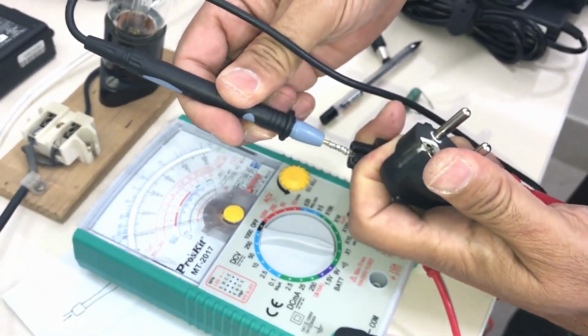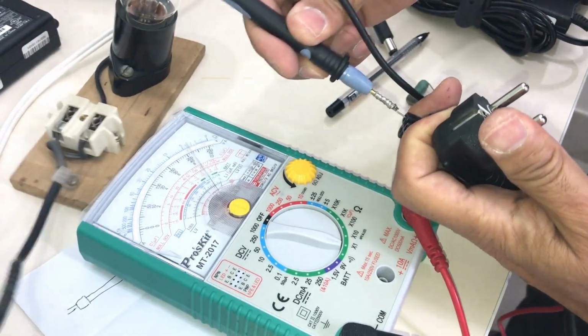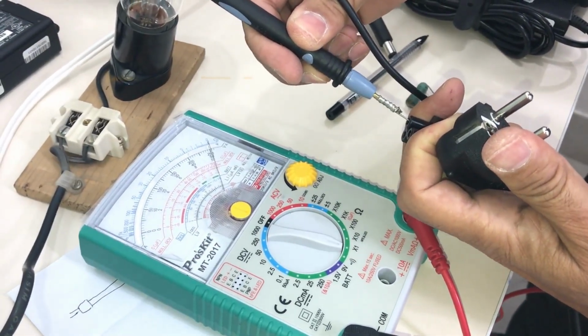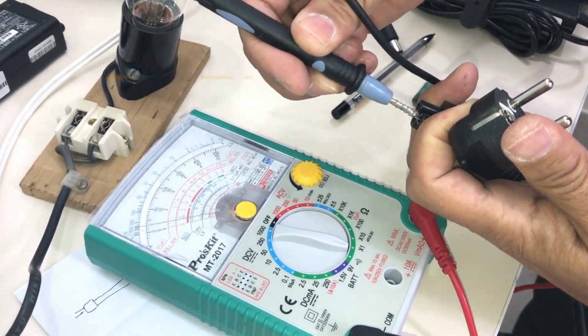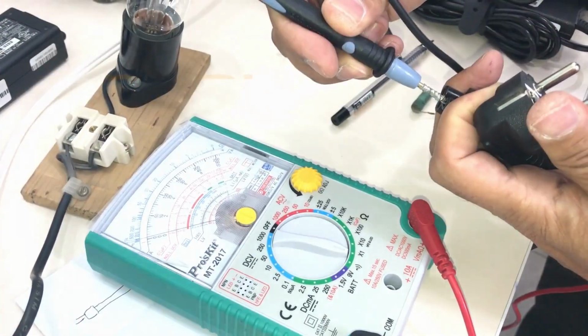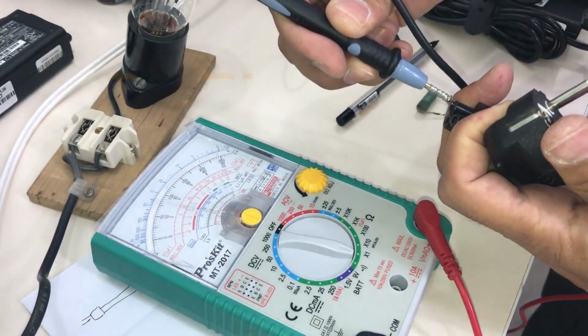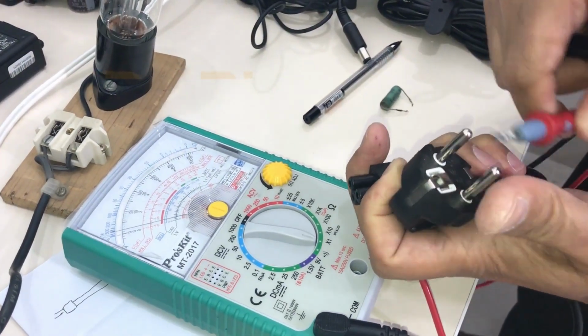Ohm meter trigger isn't moving. I try the next one, 0 appears on the ohm meter. This string is connected to this string, and doesn't have a short circuit to the other string. So we tested the short circuit and string disconnection all together. Let's test the other one.